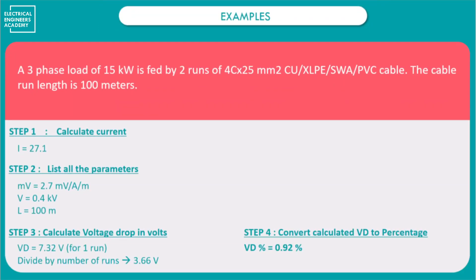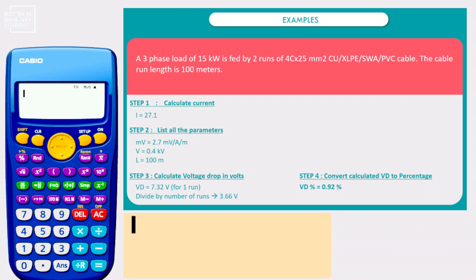Now let's go to a practical calculation example. We have a three-phase load of 15 kW connected using two runs of 4-core 25 mm² cable, with a cable run length of 100 metres. Step one is to calculate the rated current.